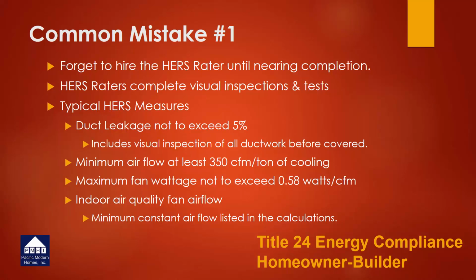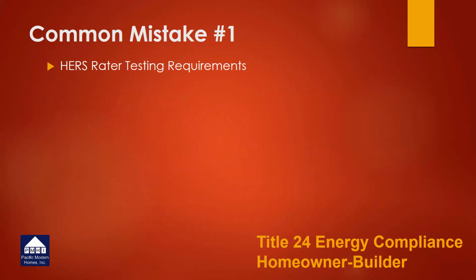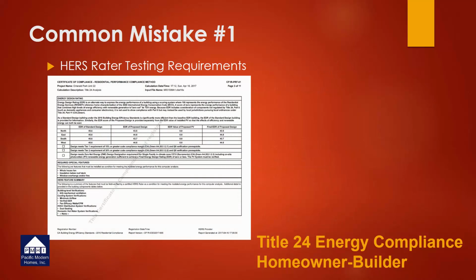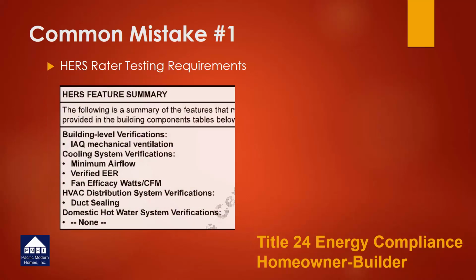Okay, so now we've looked at all of the items that are required, but how do you know for sure what's required on your HERS measures? Well, we give you a summary sheet that we told you about on the drawings, but the most authoritative form to go to for the HERS rater testing requirements is the energy calculations. And this is a typical page out of the energy calculation package. The listing is typically on page 3, and it's typically at the bottom of the page where it says HERS feature summary. If we blow this up, it becomes a little bit easier to see what's required.